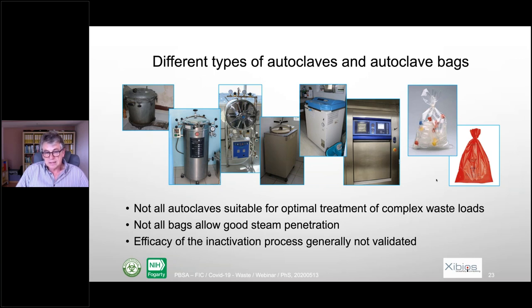The problem is that most of the time, the efficacy of the inactivation process is not validated. So perhaps we use some bioindicators and so on, but outside of the bag. So we still don't know what happens inside the bag. So there is an issue at that level. When autoclaving, if the autoclave is not appropriate, if the bags are not appropriate, if it's not validated, we are not sure that it is inactivated.